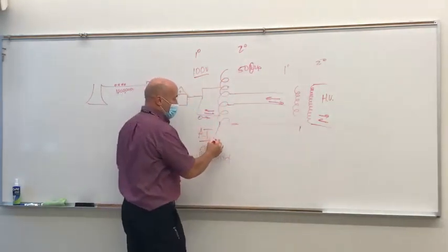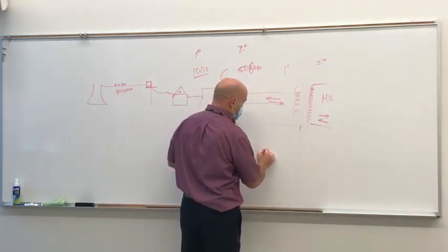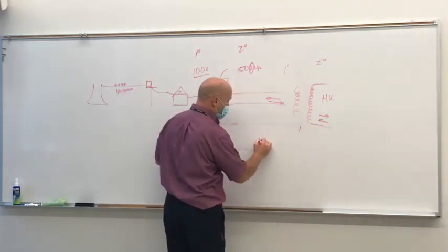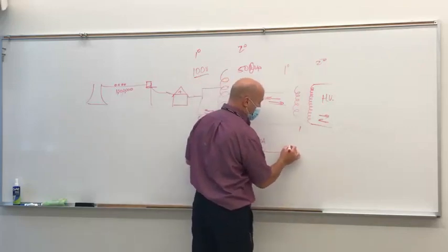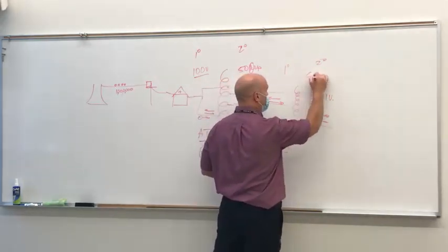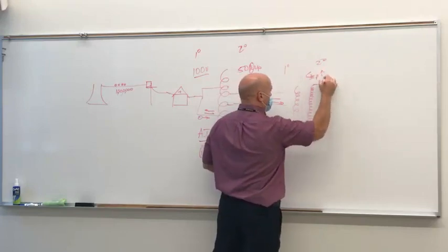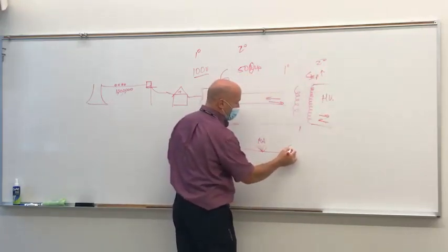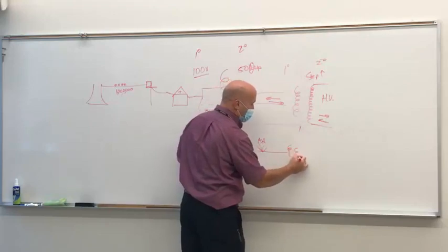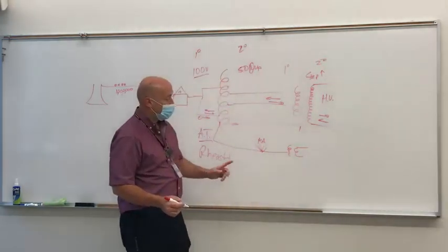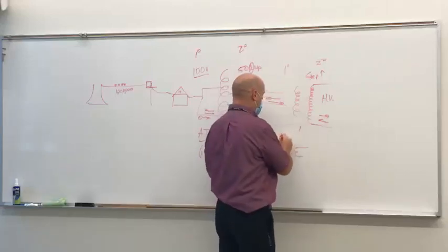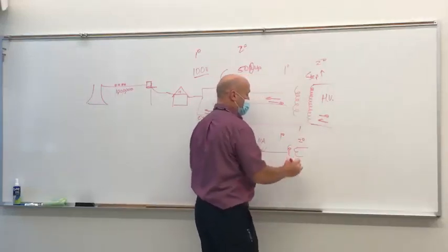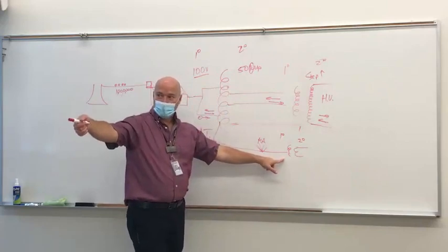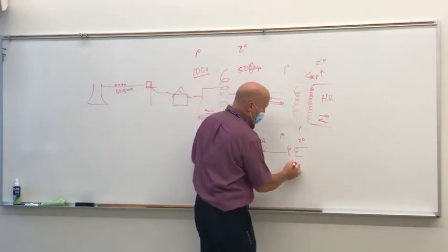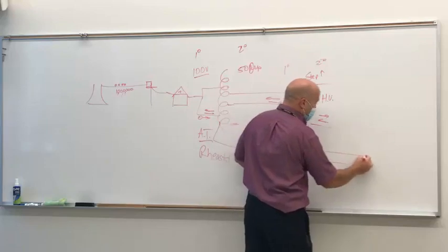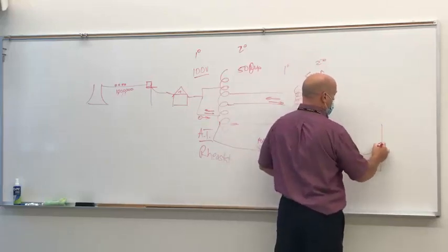At the same time, we're coming off of that, going into a filament transformer, or filament circuit, where we set our mA, and then it comes out of that and goes into a step-up transformer. So this one would be a step-down transformer, and we can tell it's a step-down transformer because it's got more turns on the primary side than on the secondary side. So this one is responsible for decreasing voltage down to maybe 10 volts, it's really 15. But then it comes out of that and it goes into the x-ray tube.